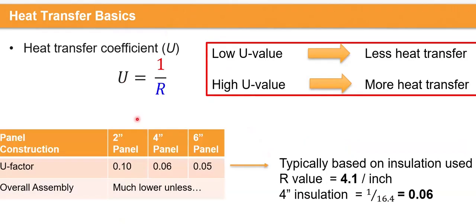And let's look at typical panel constructions as they relate to our acoustic panels. You typically see a U factor of 0.1 for 2-inch panels, 0.06 and 0.05. These are for our competitor. Well, these values are based on the insulating media only. For a typical mineral wool, the R value is 4.1 per inch. Once you multiply that for 4 inches and you do the math, you do have 0.06. So a single panel based off of the insulation alone would give you the 0.06, which you typically see in your specs. However, the overall assemblies would be much, much lower due to connections to structural and through metal connections.